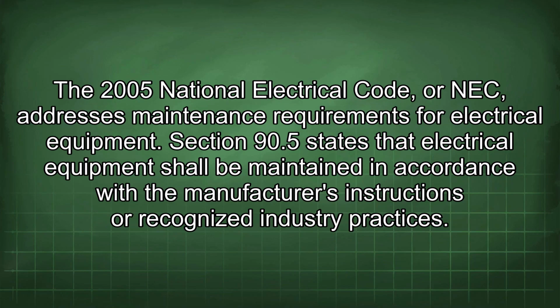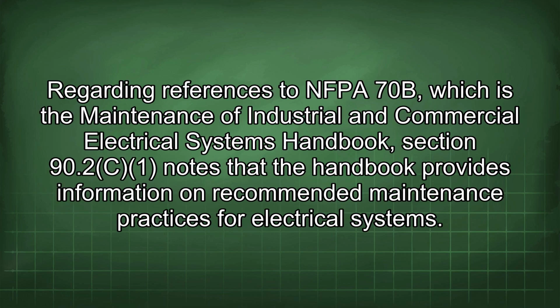The 2005 National Electrical Code, or NEC, addresses maintenance requirements for electrical equipment. Section 90.5 states that electrical equipment shall be maintained in accordance with the manufacturer's instructions or recognized industry practices. Regarding references to NFPA 70B, which is the Maintenance of Industrial and Commercial Electrical Systems Handbook, Section 90.2 notes that the handbook provides information on recommended maintenance practices for electrical systems.